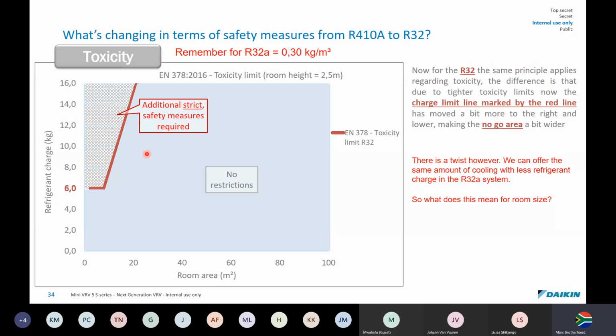Because of also the way it's been rated. So on a room up to 15 square meters, you can put more refrigerant in the system with 410A. They're a lot stricter with R32, and you can see here we have a limit of only 6 kilograms. But there's a twist. We can offer the same amount of cooling though with less refrigerant charge in the system.